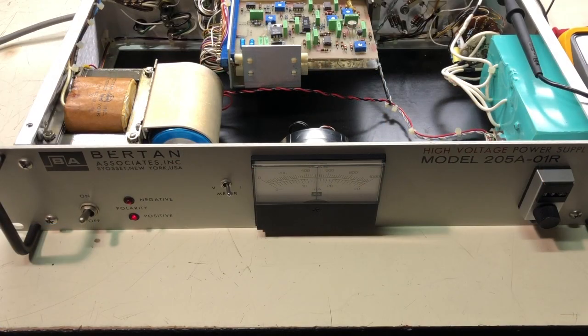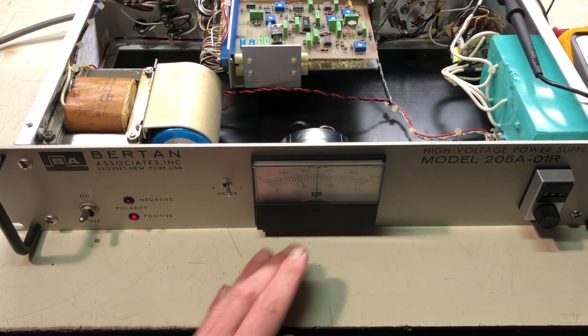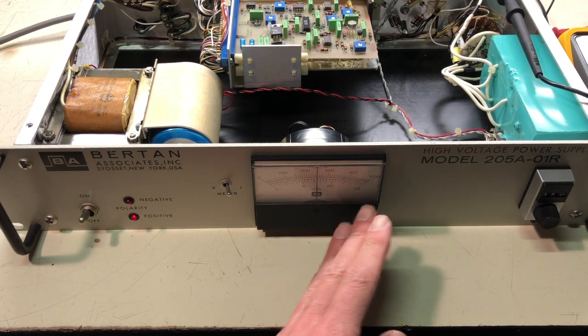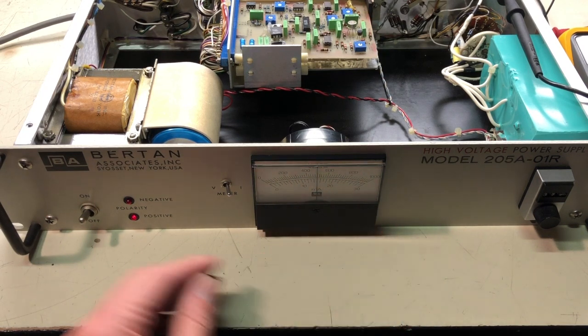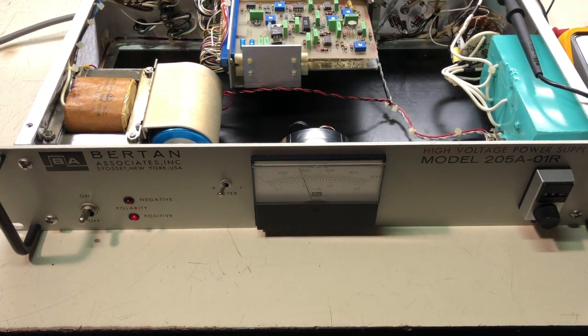Here's a better view so that you can see the meter on the front panel. You can see it's right in the mid scale, which is 15 milliamps, 30 milliamps maximum, full scale. And if I go back to the voltage, there's the 375 volts. Back to the current. So that looks really good. That's looking really good. And the meter, you can't see in the frame now, but it's holding right at 14.99, so it looks real stable, looks really good.